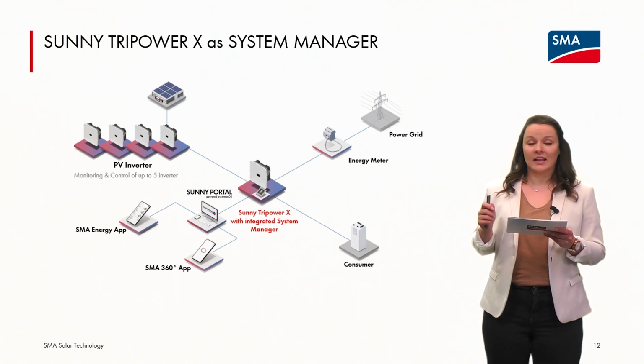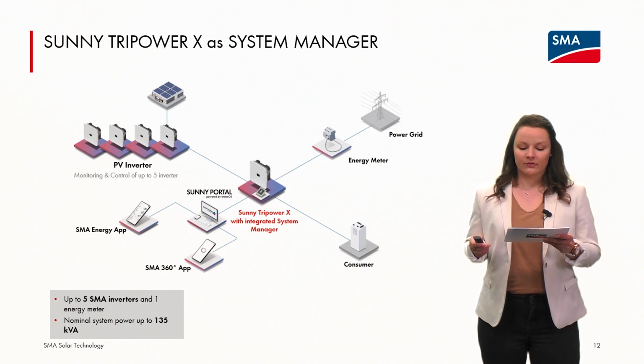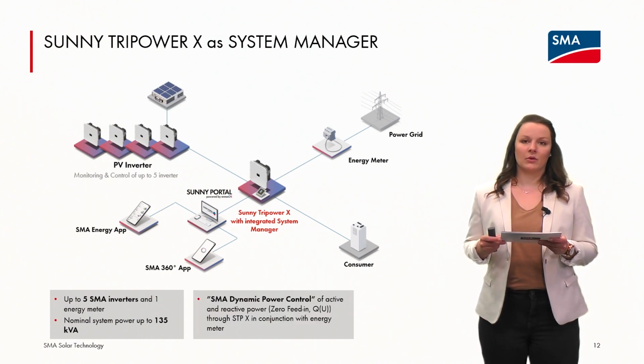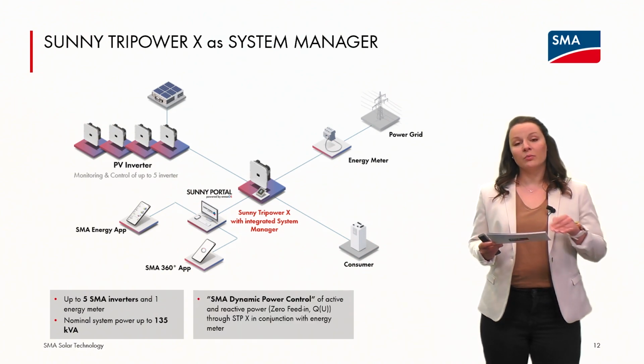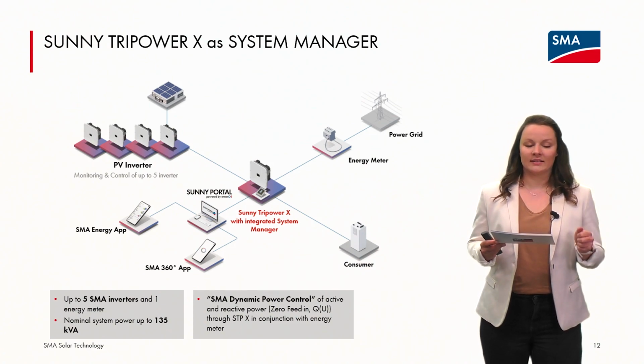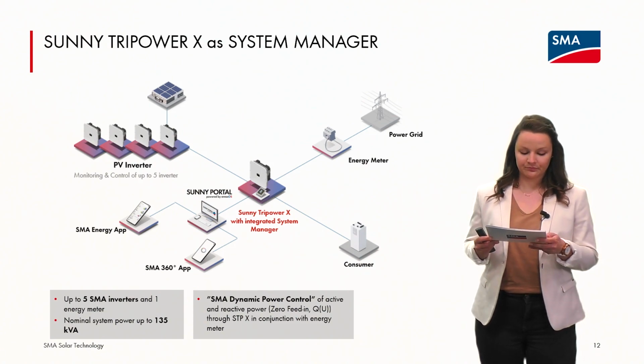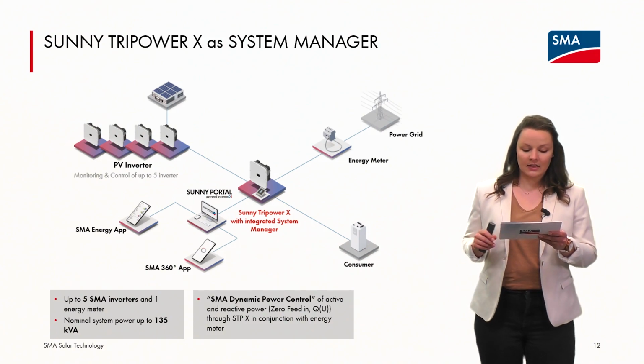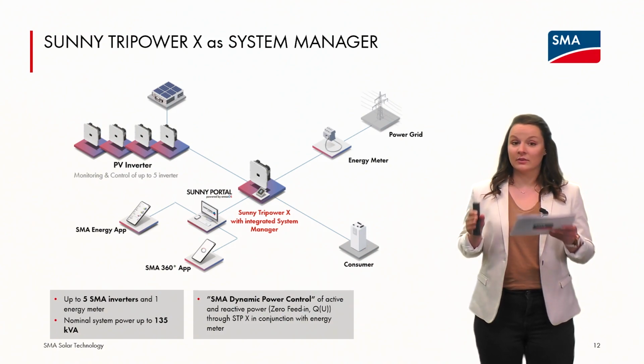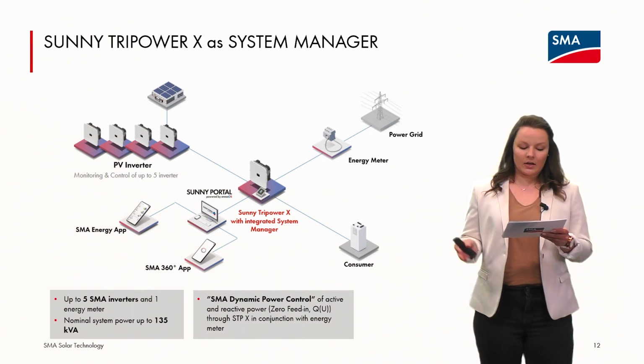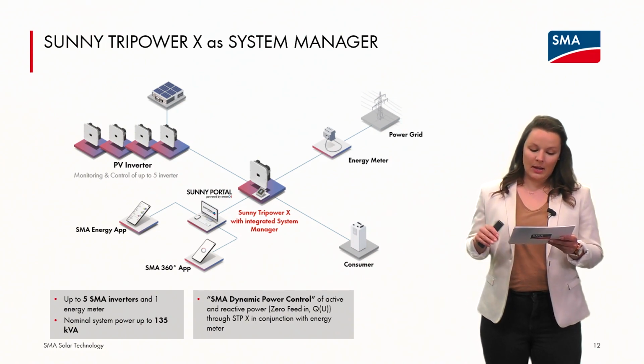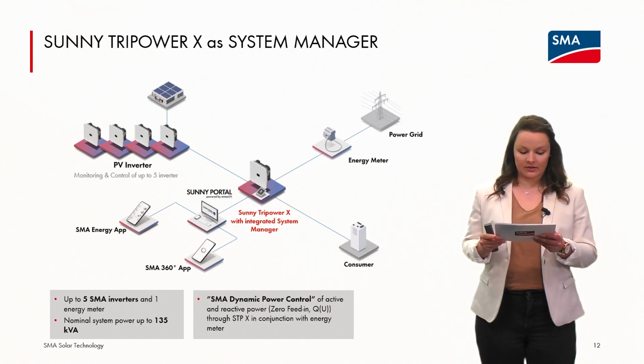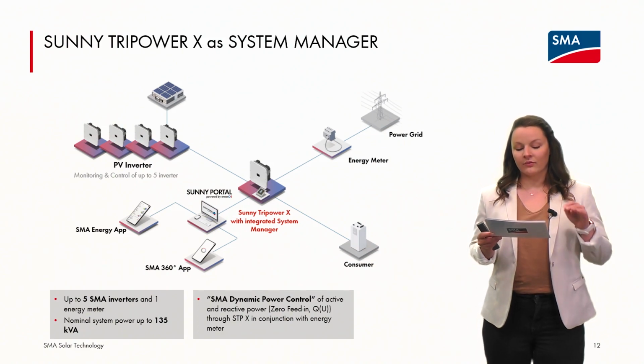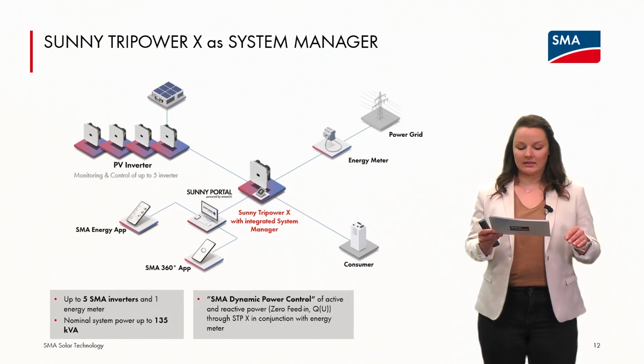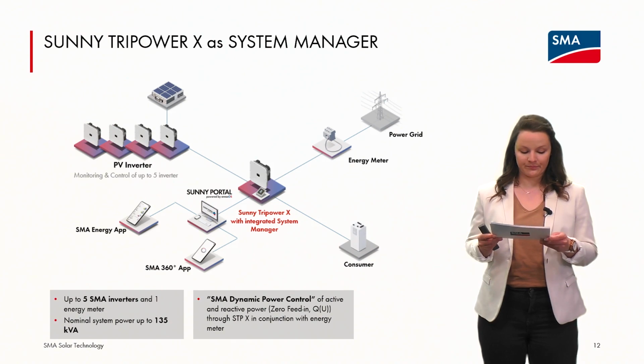If we implement an energy meter, it offers the function SMA Dynamic Power Control, meaning open and closed loop control of active and reactive power. That means, for example, if we have a zero feed-in, we can optimize the power generation by taking into account the self-consumption before the feed-in power is limited at the grid connection point.